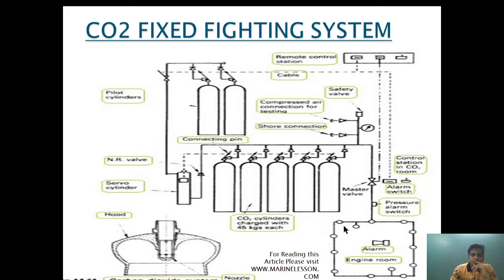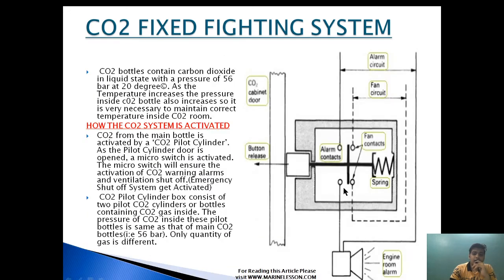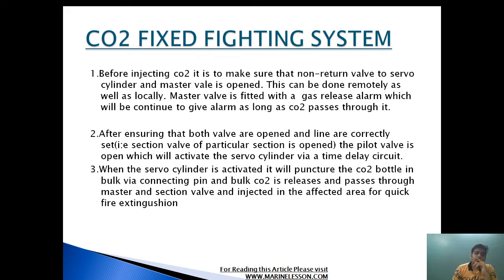After ensuring both valves are open and the line is correctly set, the section valve of the particular section is opened, and then the pilot valve is opened, which will activate the servo cylinder via a time delay circuit. After opening the master valve and section valve for the area where CO2 will be applied, the pilot cylinder bottle is punctured. The CO2 will not immediately go through to the engine room area because a time delay is provided, giving a person enough time to escape if trapped.